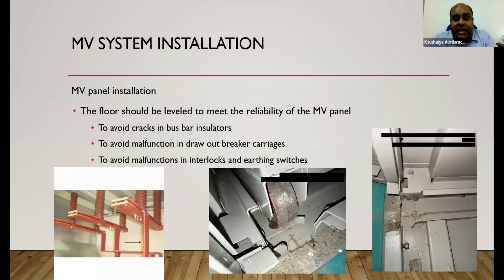During the MV panel installation, if the level is not being met, the reliability of your MV panel will drastically decrease because of crack formation of insulation or bus bar and malfunctions in draw out breakers. Sometimes you may not be able to rack it in after you rack it out. In this particular image, you see, because of not leveling the floor well, the user had to use a small washer to lift the circuit breaker to engage the interlock when racking in. That is totally because of not leveling the floor.